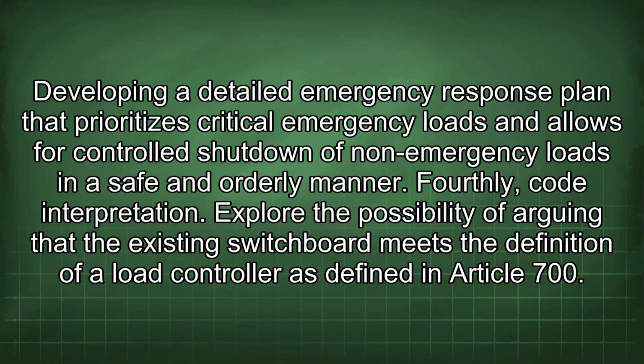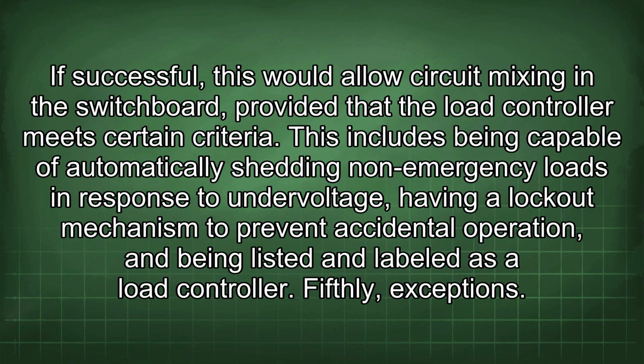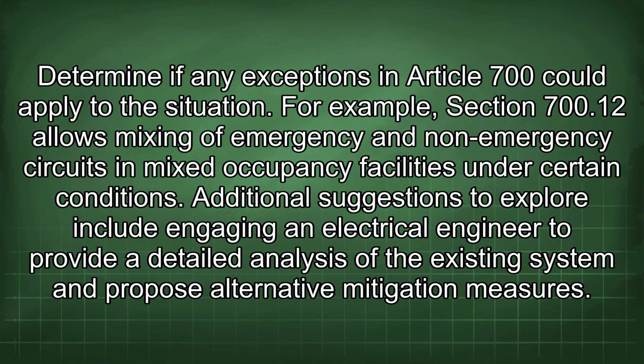Fourthly, code interpretation. Explore the possibility of arguing that the existing switchboard meets the definition of a load controller as defined in Article 700. If successful, this would allow circuit mixing in the switchboard, provided that the load controller meets certain criteria. This includes being capable of automatically shedding non-emergency loads in response to undervoltage, having a lockout mechanism to prevent accidental operation, and being listed and labeled as a load controller. Fifthly, exceptions. Determine if any exceptions in Article 700 could apply to the situation. For example, Section 700.12 allows mixing of emergency and non-emergency circuits in mixed occupancy facilities under certain conditions.